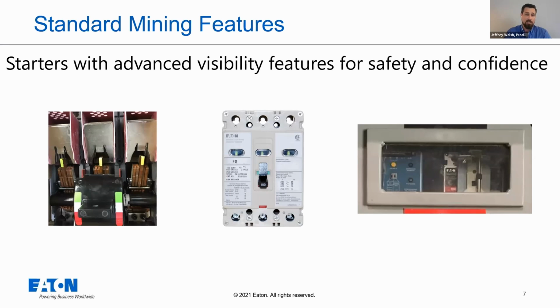But then there are also voltage indicating devices that can be installed on the enclosure. Some people want them connected to both line and load side. So you'd have A phase, B phase, C phase, all indicating lights on the device, and you can walk up to it and confirm that there's no voltage present at the line side or load side through those devices. And there are also test probe provisions that allow someone to use their meter to connect to the terminal points. Now, all of that is really just to make sure you obviously have to have the right amount of PPE on to be even in front of the enclosure, but all these things are in an effort to really reduce the hazard of anyone having the enclosure open.